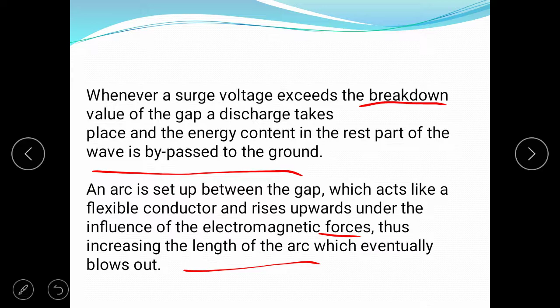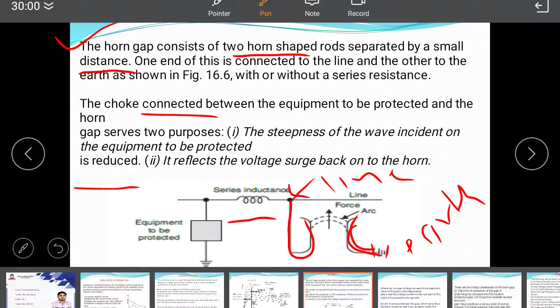So in the circuit there are two horn shaped rods. One end is connected to the line and the second is connected to the earth. There is a small gap, and in this gap there is only air. When a surge is applied on the transmission line, then in the air gap of the rods, an arc is struck because of the ionization of the gas particles.